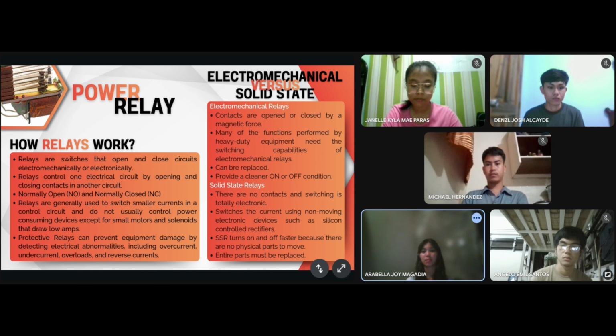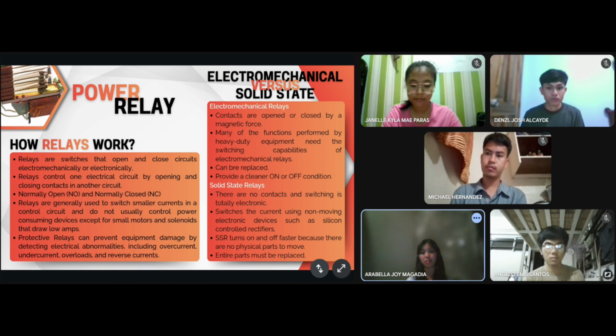On the other hand, solid state relays don't have any moving parts. Everything happens electronically using semiconductor components like transistors. So, since there are no parts to physically move, SSRs are faster to turn off and on, perfect for applications that need quick switching. However, once an SSR wears out, you cannot just replace the parts, the whole relay must be replaced.